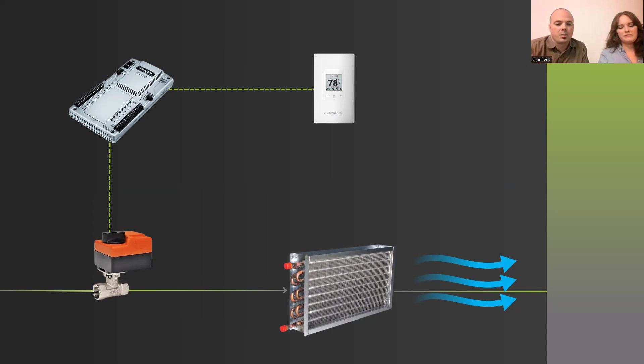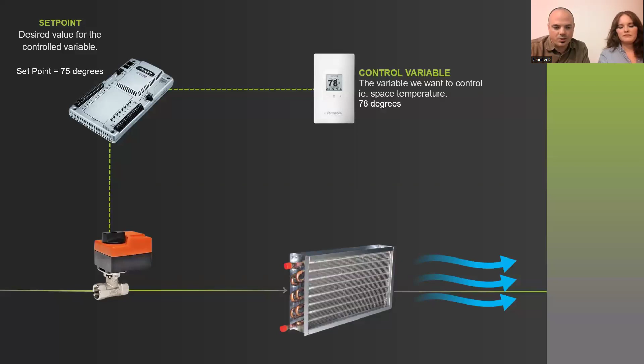So let's take it out of the metaphorical and into a pretty common HVAC controls application. We're going to go through this by defining the important components that make up a control loop. We're going to start with the control variable. This is an input device, going back to the I/O side of things. In this particular example, it's going to be a temperature sensor. We are using the temperature sensor to understand what the temperature is, but it's also our guiding point for whether or not we're doing the thing we want to do. Next is the set point. In this example, the set point is 75 degrees and the control variable is currently at 78 degrees.